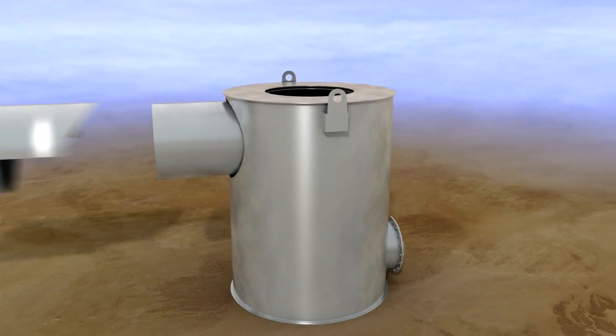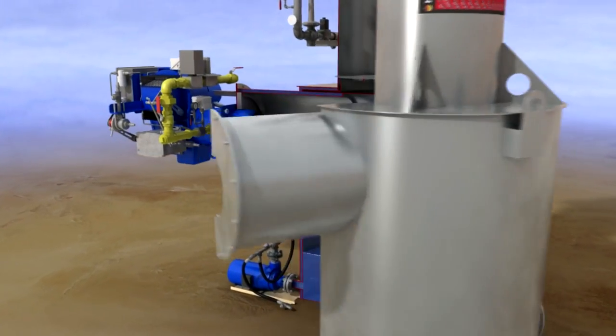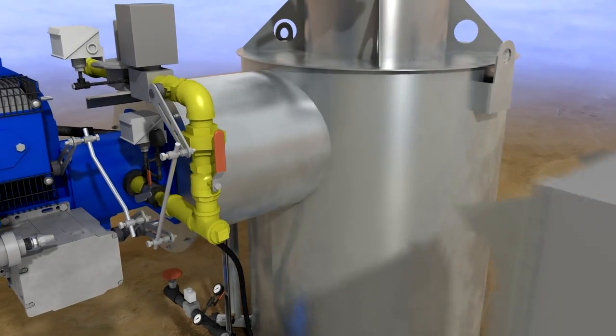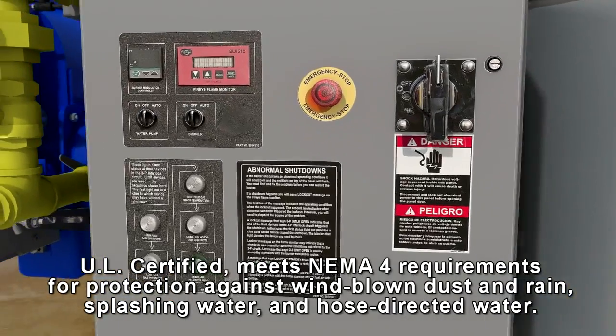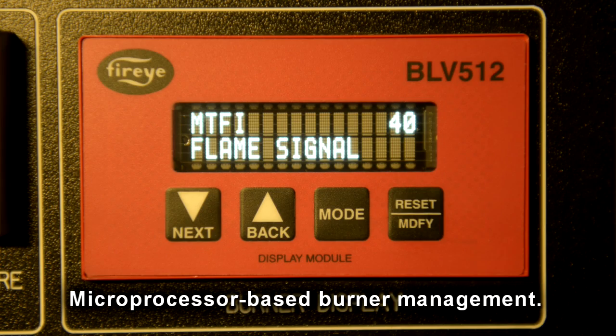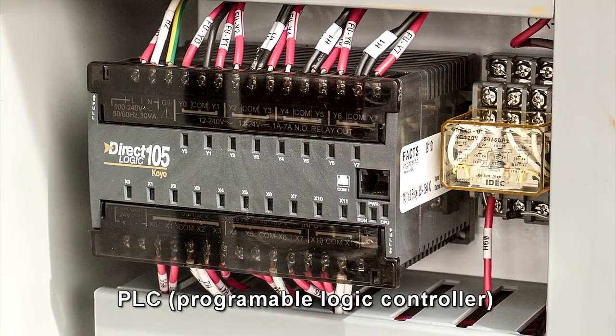Key components of Firestorm heaters are shell, piping, and internal parts made of stainless steel, special stainless steel packing, and burners that operate on natural gas and propane — Low NOx burners are optional. A water jacket protects the burner housing and heater shell from overheating. A control panel that is UL certified meets NEMA 4 requirements for protection against wind-blown dust and rain, splashing water, and hose-directed water. A Fireye flame monitor provides microprocessor-based burner management, with controls automated using a PLC, programmable logic controller.